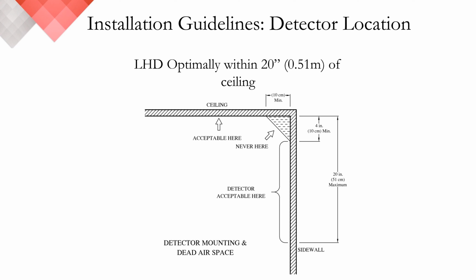The corner, where the ceiling and the wall meet, forms an area known as the dead air space, as shown here. This dead air space is the triangular area formed along the ceiling by measuring 4 inches or 10 centimeters out from the corner and 4 inches, again 10 centimeters, down the sidewall. Protectowire should not be placed in this area.